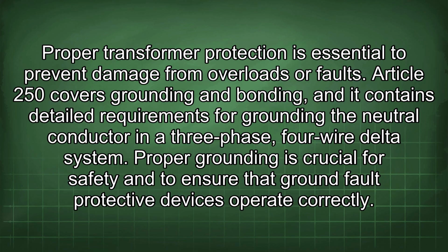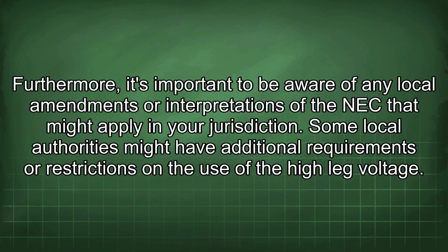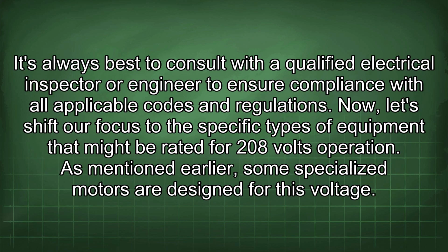Article 250 covers grounding and bonding, and it contains detailed requirements for grounding the neutral conductor in a three-phase, four-wire delta system. Proper grounding is crucial for safety and to ensure that ground fault protective devices operate correctly. Furthermore, it's important to be aware of any local amendments or interpretations of the NEC that might apply in your jurisdiction. Some local authorities might have additional requirements or restrictions on the use of the high leg voltage. It's always best to consult with a qualified electrical inspector or engineer to ensure compliance with all applicable codes and regulations. Now, let's shift our focus to the specific types of equipment that might be rated for 208 volts operation.